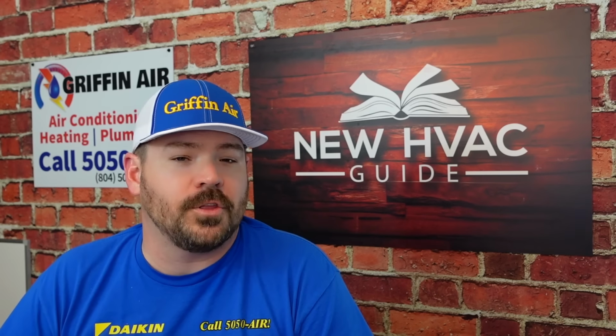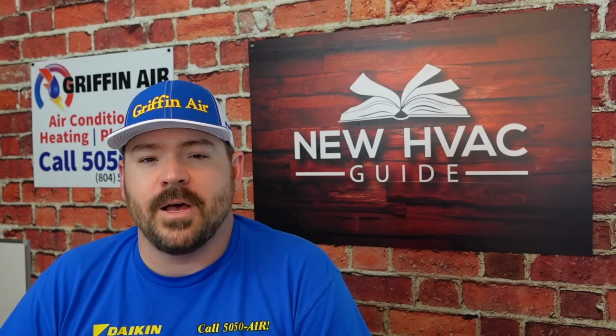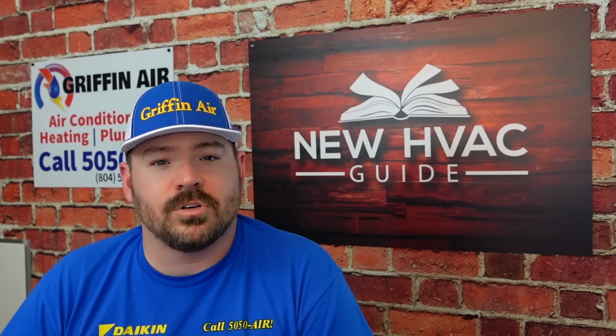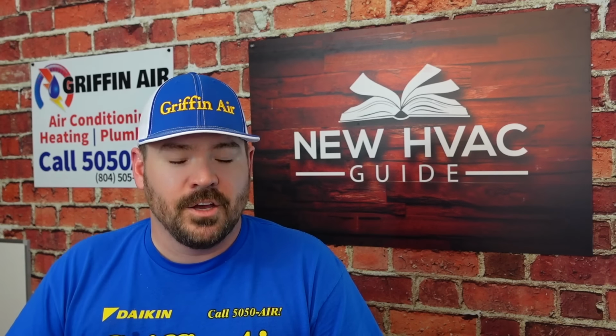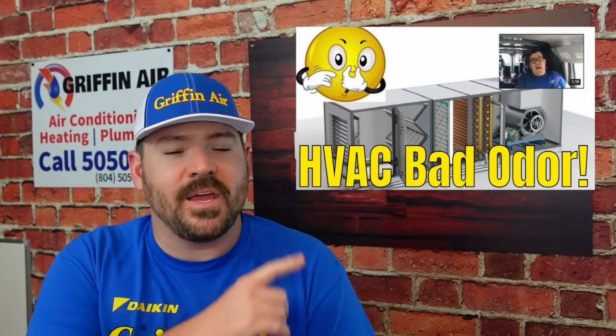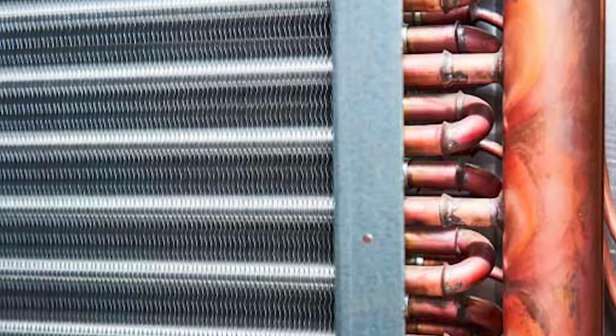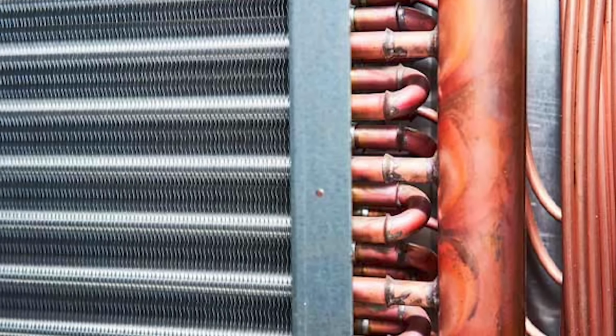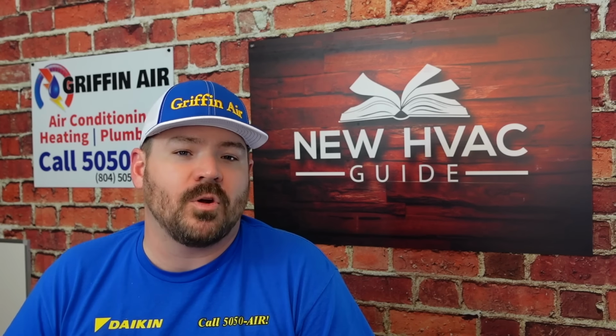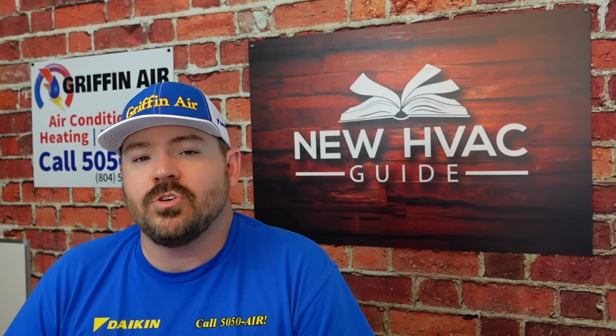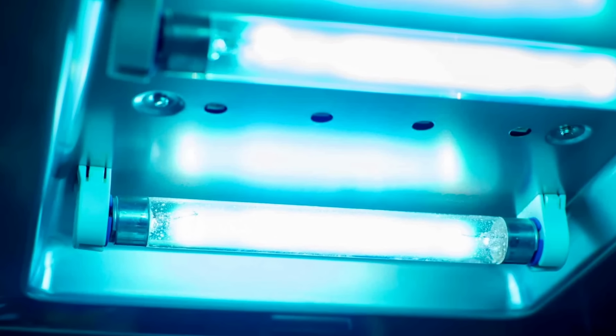Next is an odor we call the dirty sock syndrome, one you're only going to smell in certain times of the year and really only in certain parts of the country. We did a whole video years ago, one of my first videos, called the dirty sock syndrome, and I'm going to put that up here. Ultimately, if you have dirty sock syndrome happening, it's usually an issue with the evaporator coil. A stagnant water type smell could be causing it, and we've even seen it happen on brand new systems. There's a number of things you can do, such as installing UV lights and possibly running an extended fan run time to dry out that coil every time the air conditioning turns on.